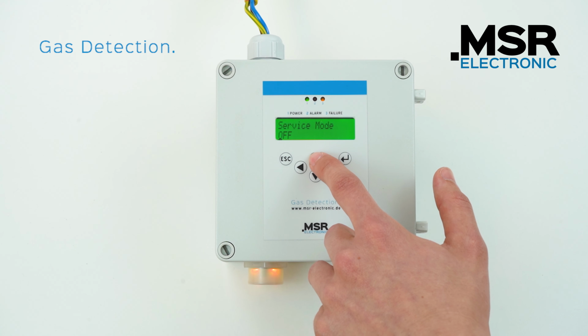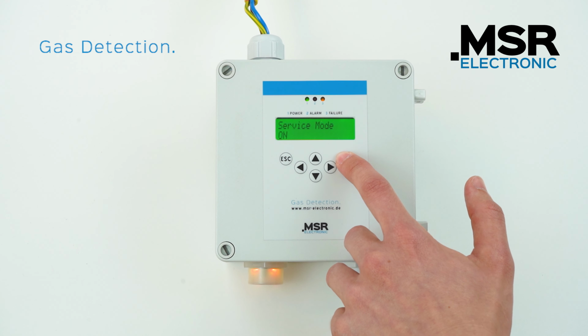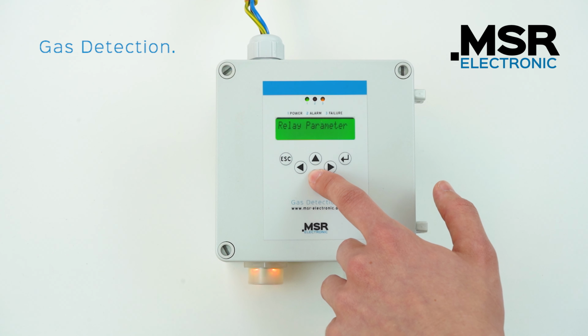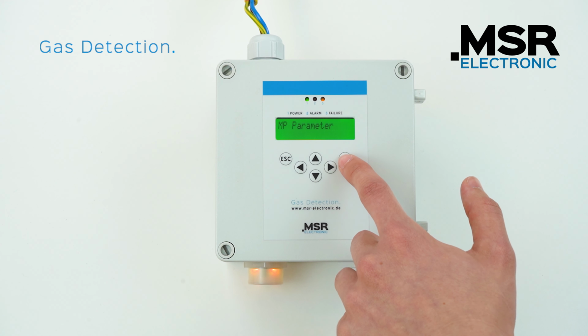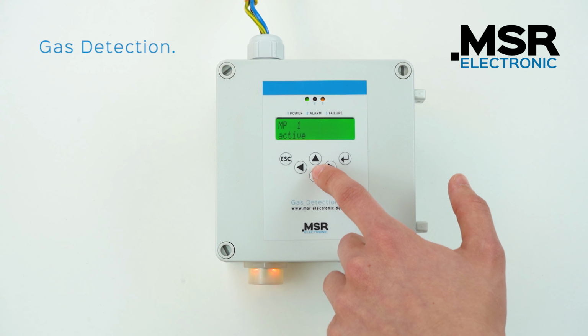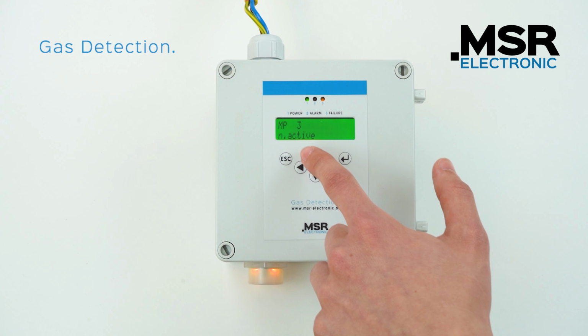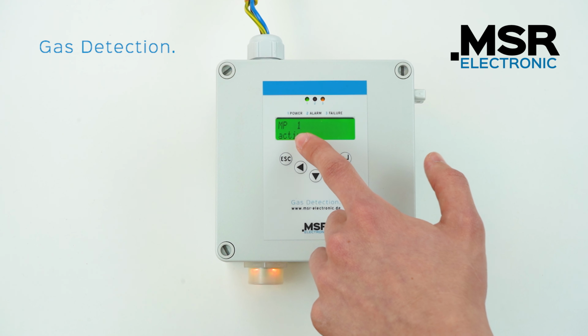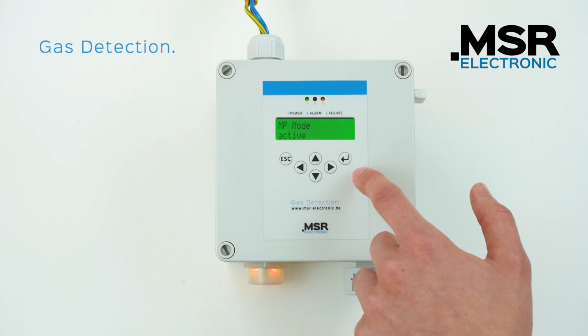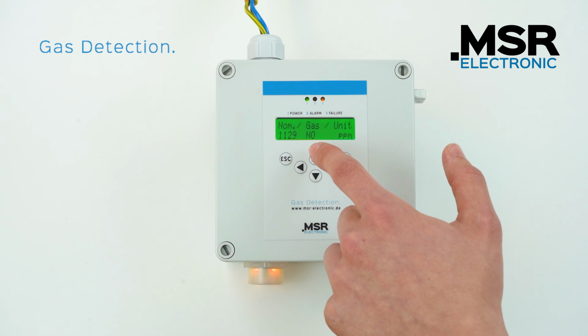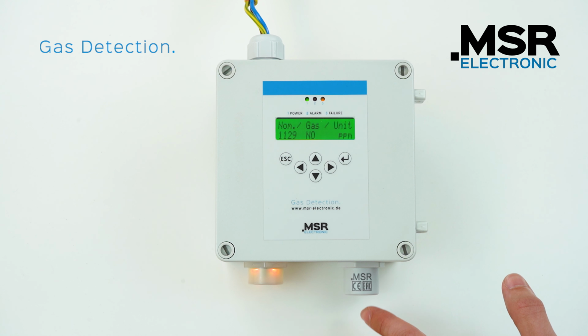Next, navigate to the MP parameters and select the measuring point at which the sensor with a communication error is to be addressed. In this case, this is measuring point 1. The measuring point at which the communication error is present can be seen in the error status.